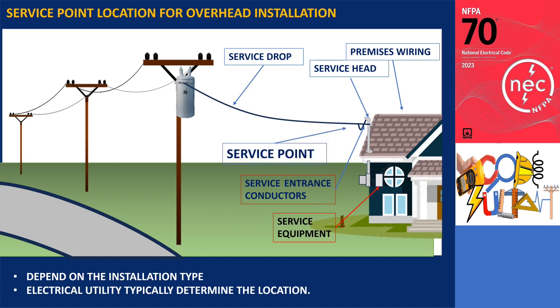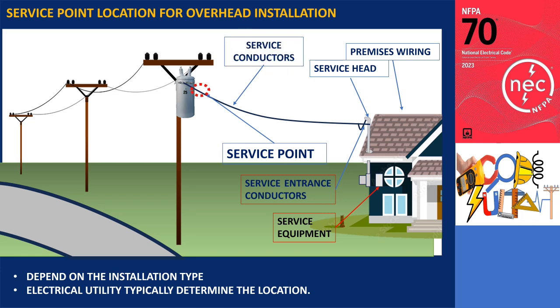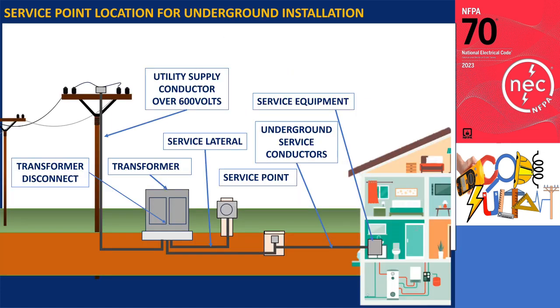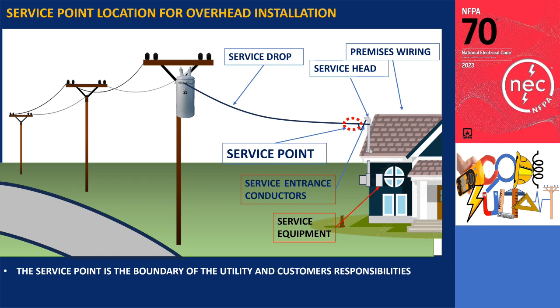The service point can be found near the service entrance or extend only up to the transformer disconnect in certain scenarios. For underground installations, the service point may be situated in the handhole or extend only up to the transformer disconnect. The service point serves as the dividing line between the utility's responsibility and the customer's responsibility. Moreover, the associated terminology undergoes changes depending on the location of the service point.